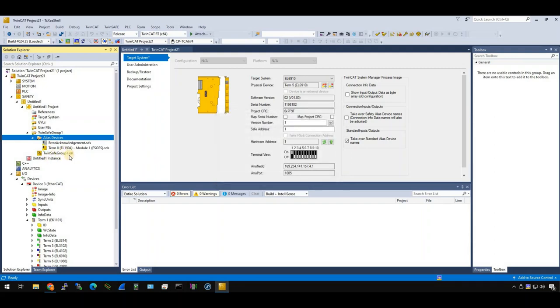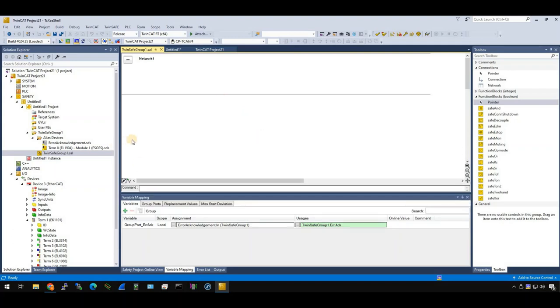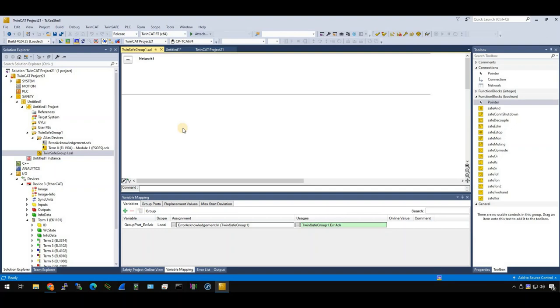So the next step, we can create some safety program. Just click the safety TwinSafe group 1. So here is the editor of TwinSafe. If you use Siemens before, you know that Siemens can allow you to configure the safety program by using ladder or FBD. But in TwinSafe, it only allows you to use FBD. Not like FBD, I think it's something like CFC, but it's not a big deal. You can do it. And I will not upload some difficult program in my first TwinSafe tutorial. I will just use the E-Stop function to get the signal from safety logic terminal, and then use the AND-NOT safety AND block to output and feedback to our standard PLC. Let's start.